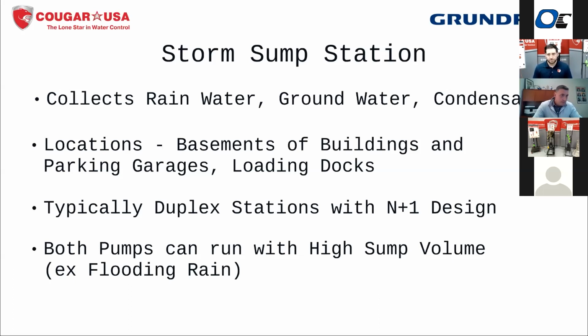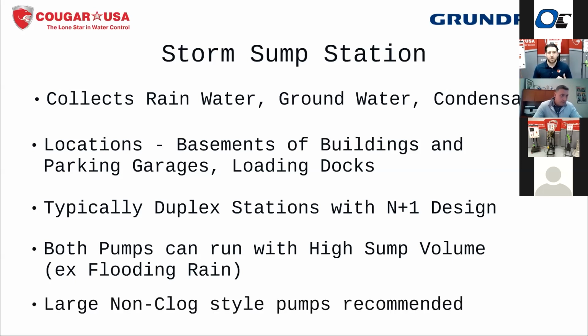So the other thing here is we're going to use large non-clog style of pumps for these. And I've got examples of what those impellers look like, both an open channel design where the water is flowing through the impeller, and then a vortex style impeller where it's actually kind of pulling that water through. It's not actually passing through the impeller. So both of those are going to be able to handle solids that might get into that pit, but they're going to move large volumes of water pretty efficiently and be good applications for the storm. Okay.